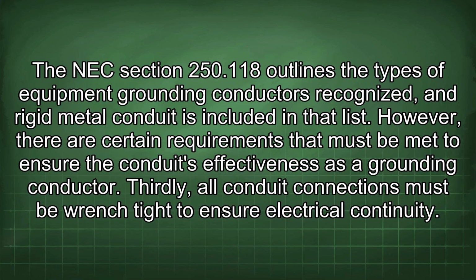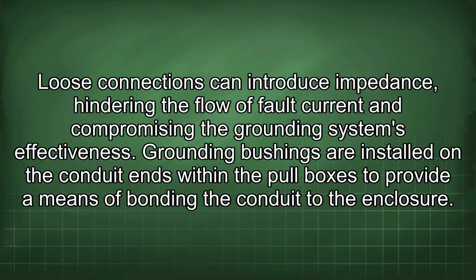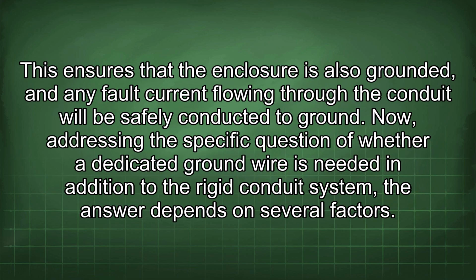Thirdly, all conduit connections must be wrench tight to ensure electrical continuity. Loose connections can introduce impedance, hindering the flow of fault current and compromising the grounding system's effectiveness. Grounding bushings are installed on the conduit ends within the pull boxes to provide a means of bonding the conduit to the enclosure. This ensures that the enclosure is also grounded, and any fault current flowing through the conduit will be safely conducted to ground.